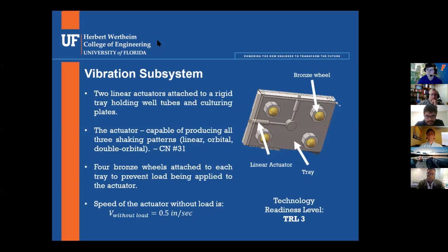Okay. So if you're going to have oil impregnated bronze, can you think of any issues with putting oil into a region with biological systems? Yeah, there definitely could be some contamination issues. I think changing the material of those wheels is something we're definitely going to look into. Take a look at it.